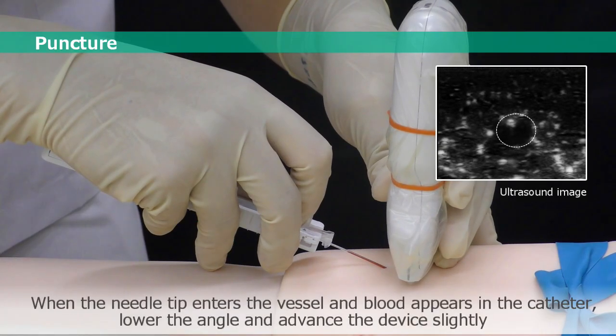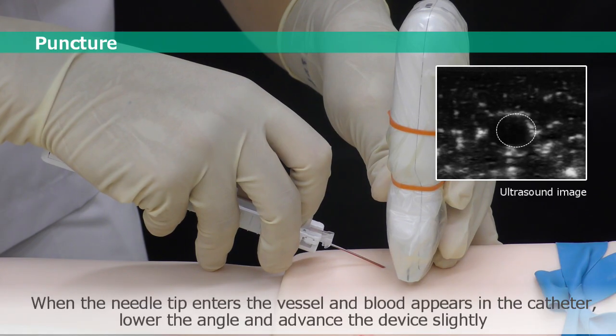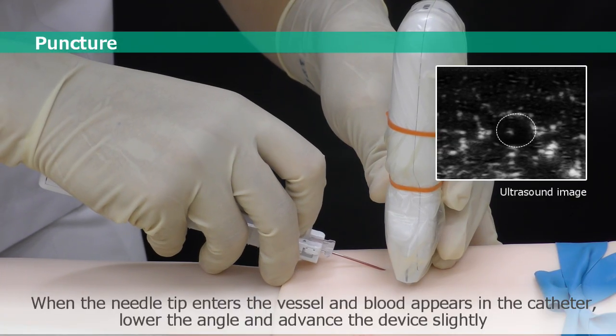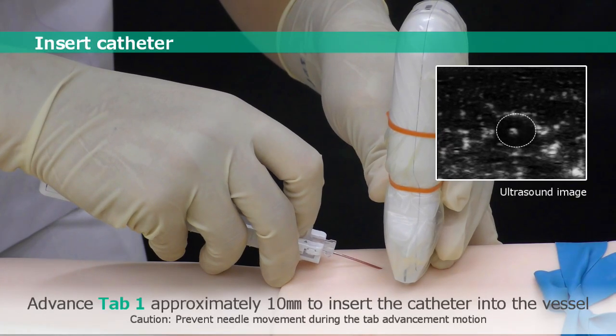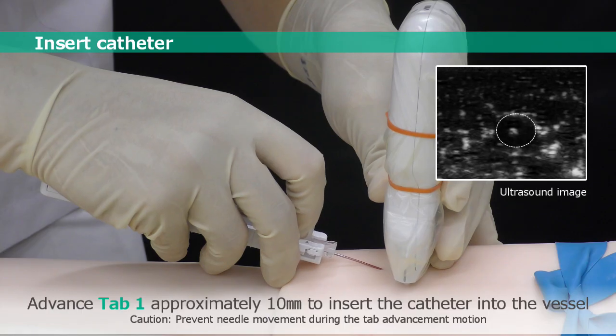Once the needle tip enters the vessel and blood return is observed in the catheter, reduce the puncture angle and advance the assembly by 1 to 2 millimeters so that the catheter tip enters the vessel. While firmly holding the main grip, advance tab 1 approximately 10 millimeters to insert the catheter into the vessel.